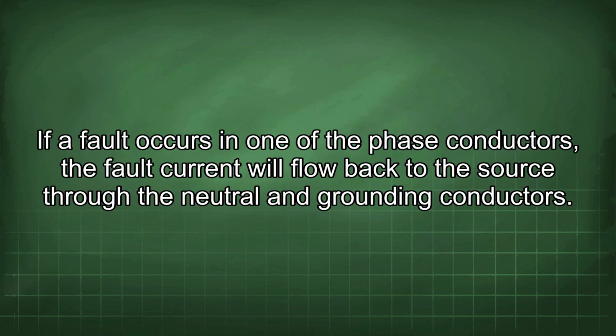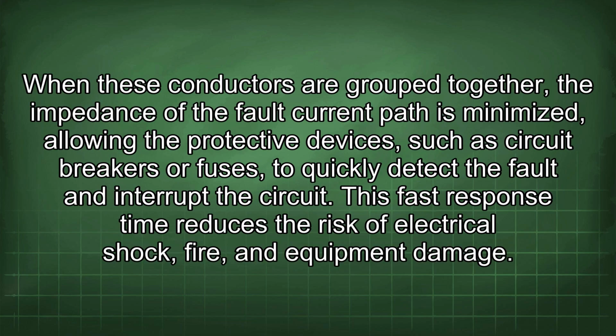If a fault occurs in one of the phase conductors, the fault current will flow back to the source through the neutral and grounding conductors. When these conductors are grouped together, the impedance of the fault current path is minimized, allowing the protective devices, such as circuit breakers or fuses, to quickly detect the fault and interrupt the circuit. This fast response time reduces the risk of electrical shock, fire, and equipment damage.